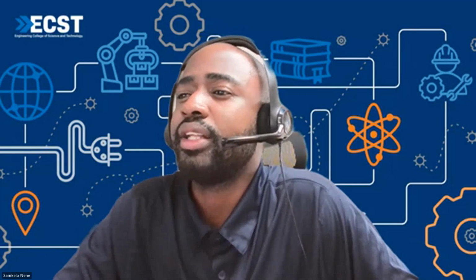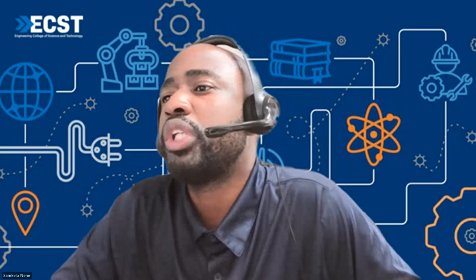These are some of the technologies that we mentioned. I did mention that if we look at hydro plants, they are good when it comes to backup. Also, the battery energy storages tend to respond faster, however for short duration, when there is some frequency deviation. Whereas hydro is mature and large scale, so it can even be used for much longer duration to stabilize the system.